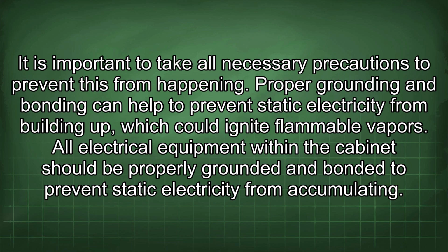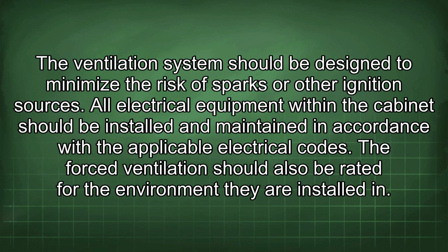Proper grounding and bonding can help to prevent static electricity from building up, which could ignite flammable vapors. All electrical equipment within the cabinet should be properly grounded and bonded to prevent static electricity from accumulating. The ventilation system should be designed to minimize the risk of sparks or other ignition sources. All electrical equipment within the cabinet should be installed and maintained in accordance with the applicable electrical codes. The forced ventilation should also be rated for the environment it is installed in.